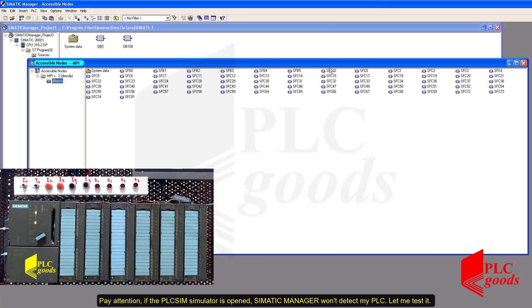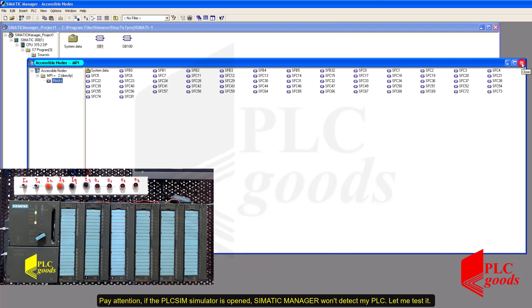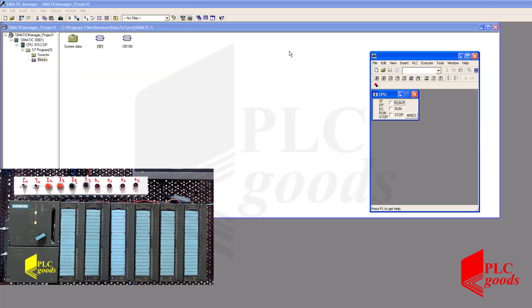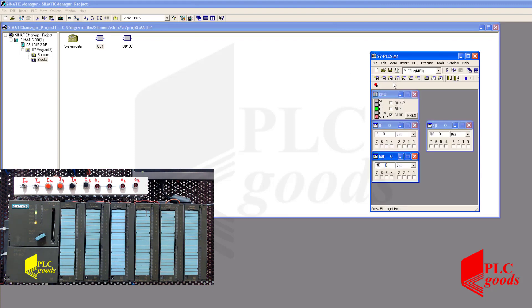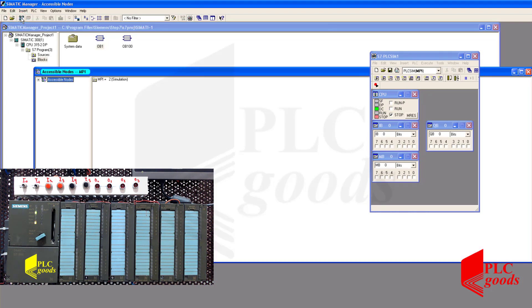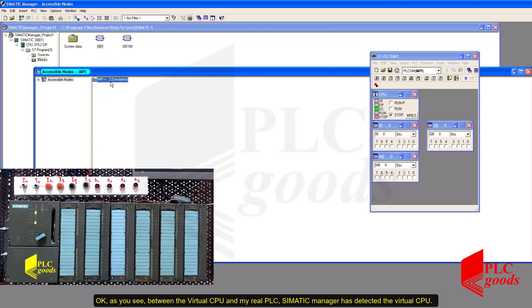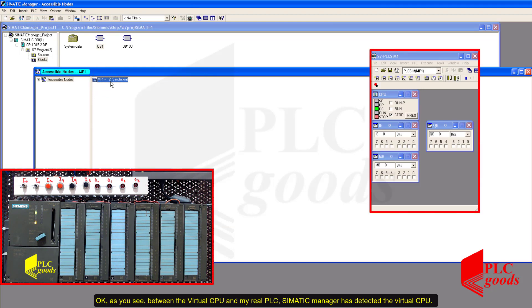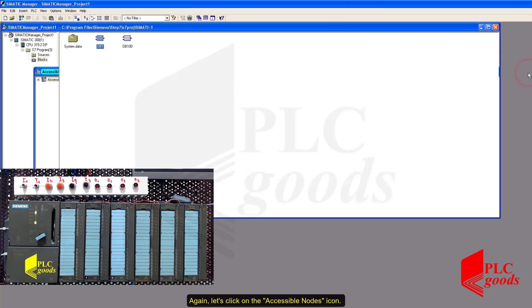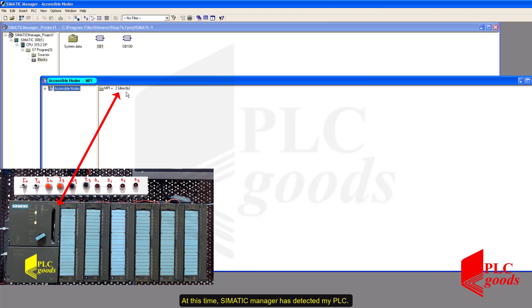Pay attention: if the PLC SIM simulator is opened, Simatic Manager won't detect my PLC. Let me test it. As you see, between the virtual CPU and my real PLC, Simatic Manager has detected the virtual CPU. I need to close all virtual CPUs to have a connection with my PLC. Again, let's click on the Accessible Nodes icon. At this time, Simatic Manager has detected my PLC.